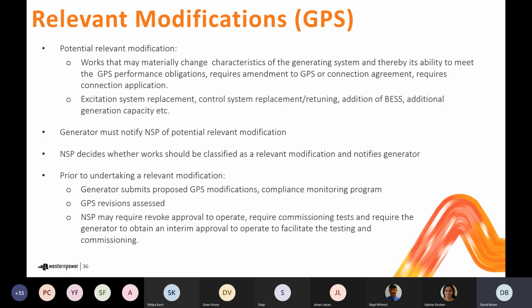The next thing then is, well, what happens if at some time in the future the owner of that large generating system decides to modify the generator in some fashion. And what we have done now is we've introduced the relevant modification framework into the technical rules to cater for that scenario. So the relevant modification framework requires that prior to undertaking a potential relevant modification, the generator needs to advise the NSP of the intended modification. So what do we mean by a potential relevant modification? Well, that's any works that may materially change characteristics of the generating system and thereby its ability to meet its generating performance standard obligations, or require amendments to the GPS or the connection agreement, or require amendment to the connection application.